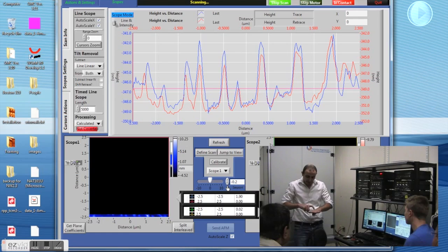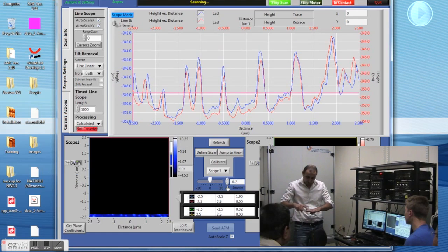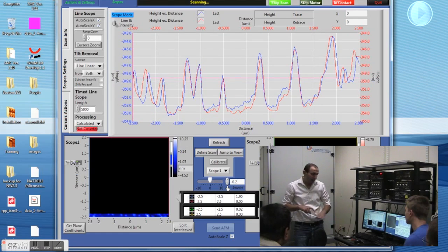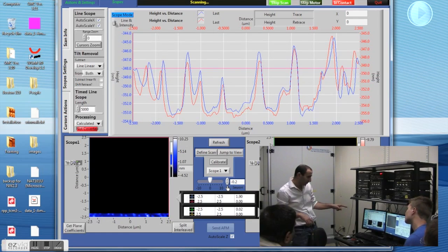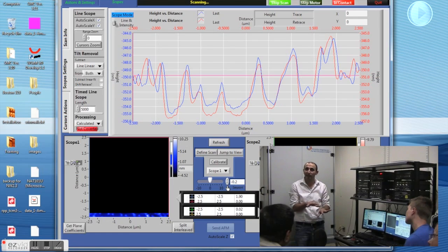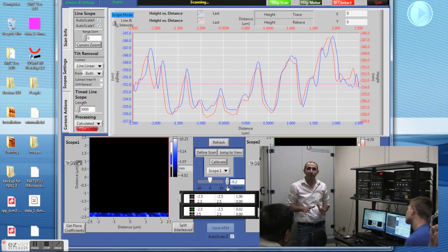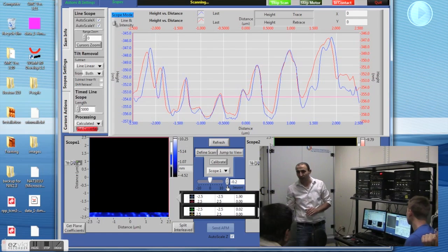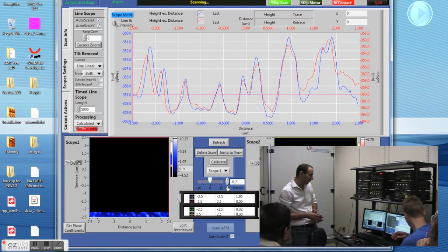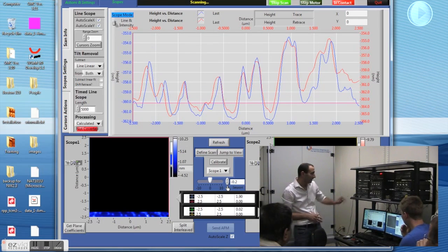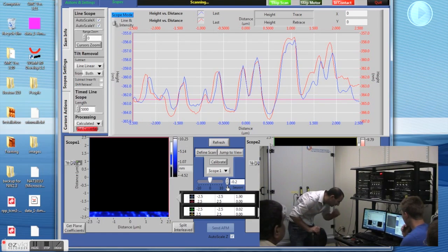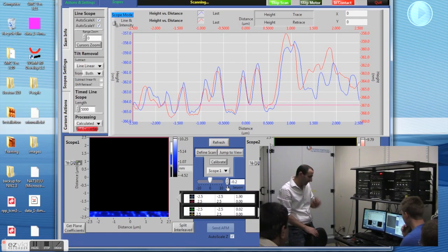So every line is scanned twice, from left to right and then from right to left, and then moving one pixel in, again left to right, right to left. The advantage of having these two lines is important in AFM, because you can correlate between them, to see if they're matching or similar. Sometimes if you have an artifact or noise, it appears in the trace and doesn't appear in the retrace. So you could easily adjust the gains and optimize your AFM setup based on that. So this is the AFM image being acquired. We'll wait a few more lines to see what's going on.